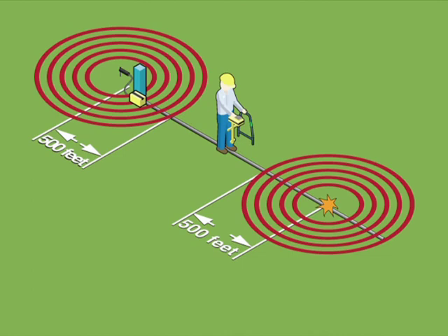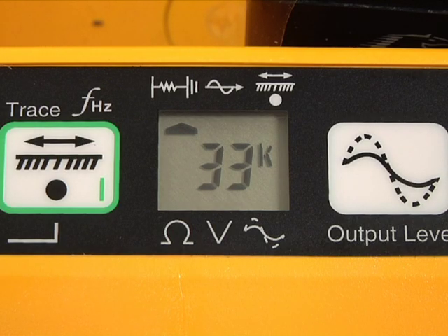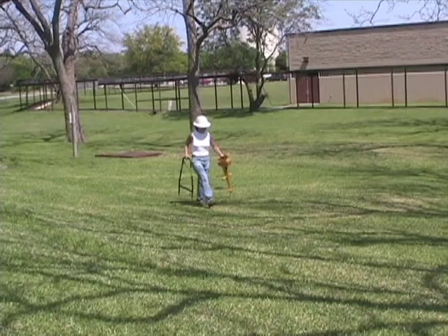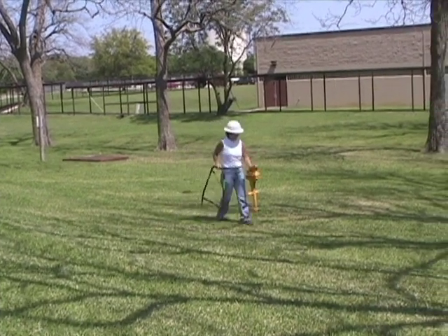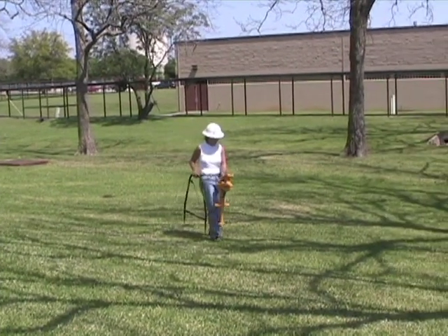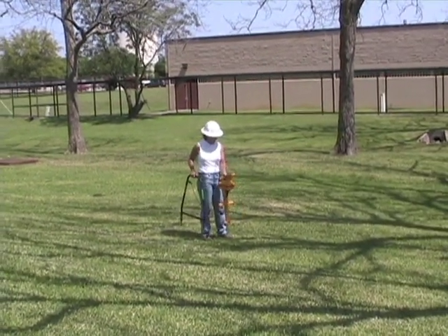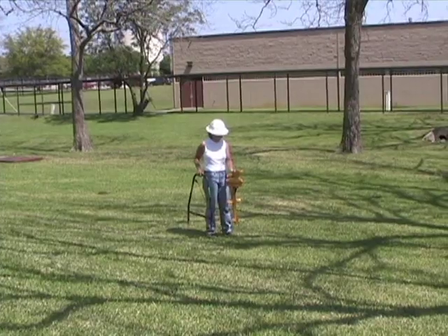This dead zone will continue until you are within 500 feet of the fault. Then you will begin detecting the fault again because you have entered the fault pool. The transmitter sends two locating frequencies, 577 Hz and 33 kHz, simultaneously with the fault locating signal. These locating frequencies can help you get through the dead zone and stay on the cable path until you get closer to the fault, or walk back into the second fault pool.